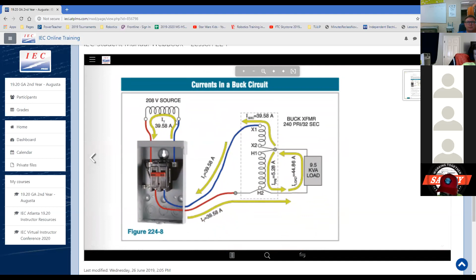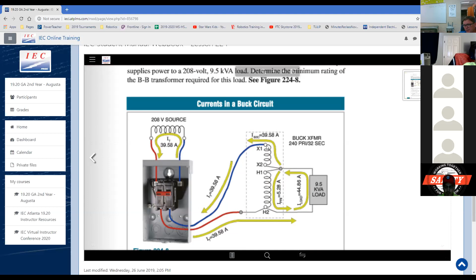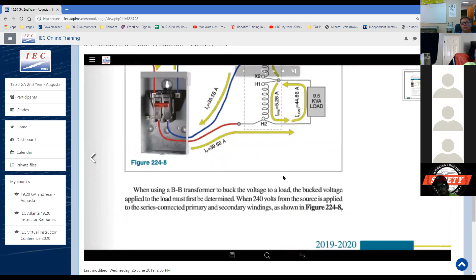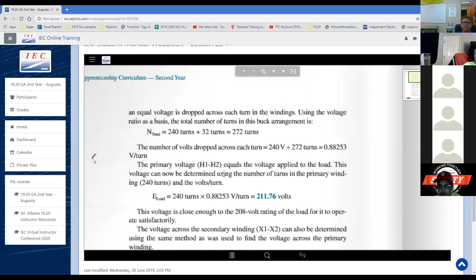So if you look at this, this is an example where we actually need it to be 208 running through, but the source is 240, so we need to make this a buck of 32 in the secondary, and that's where we get 240 minus 32 is 208. It's going to be a little bit weirder numbers when you see it in just a second. This one's not as bad to me. That's the one we just did.